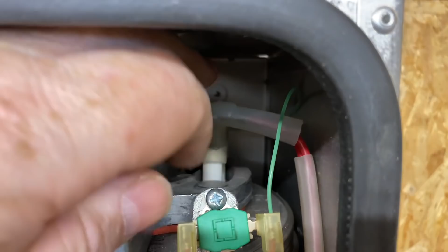Normally I try and take this off, so I gently take this front wire off on the electrodes. You need to be really careful with these because they split sometimes, and this one has - you can see it's snapped off on top there, the covering. So we'd have to get a new set of leads if we were repairing this boiler.